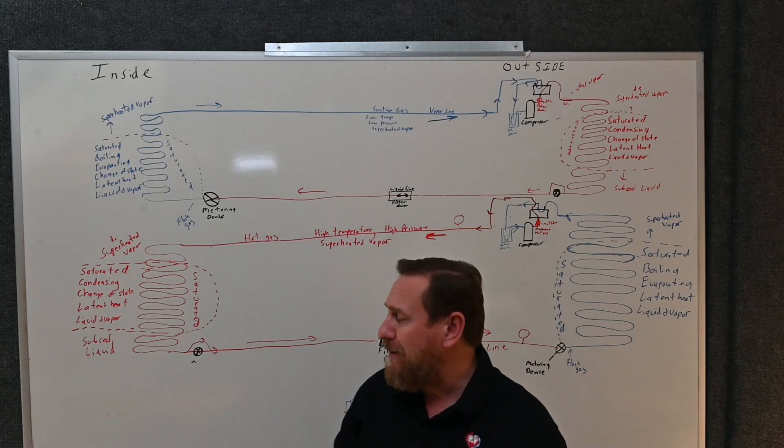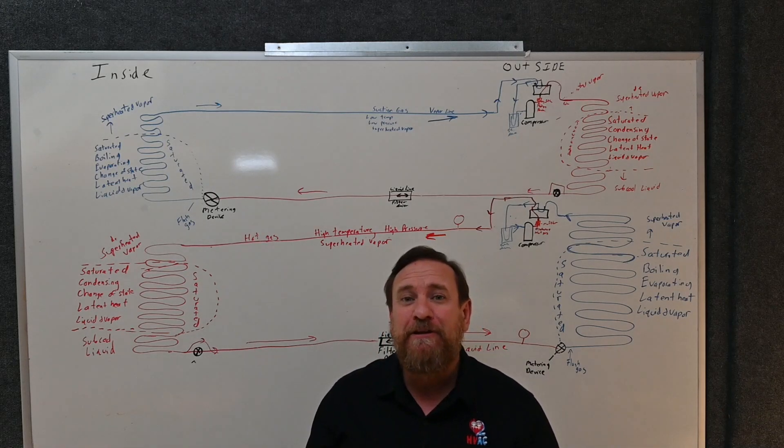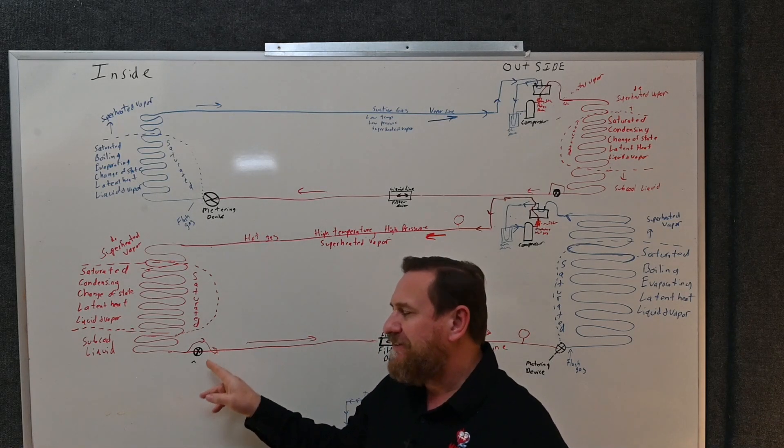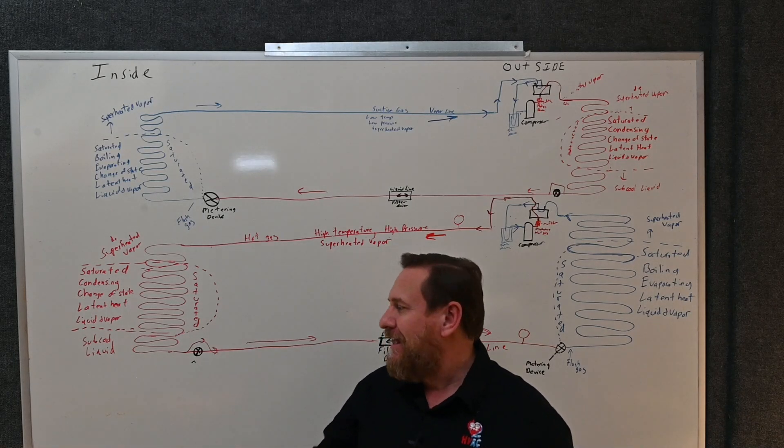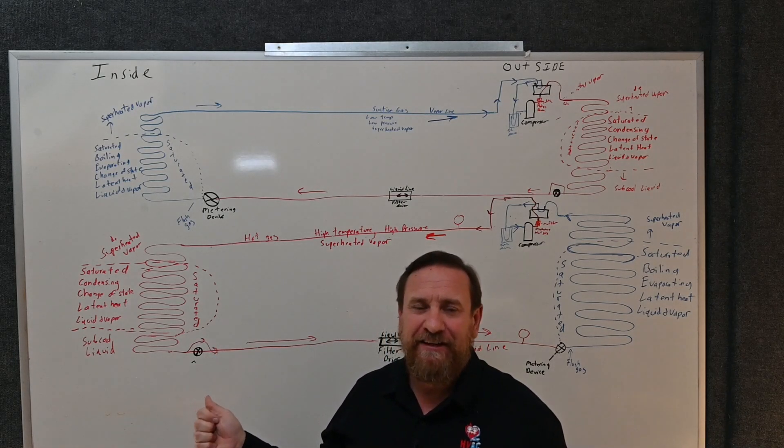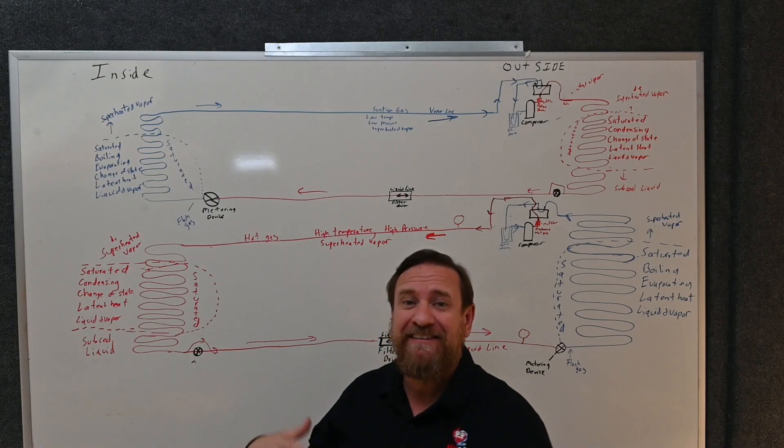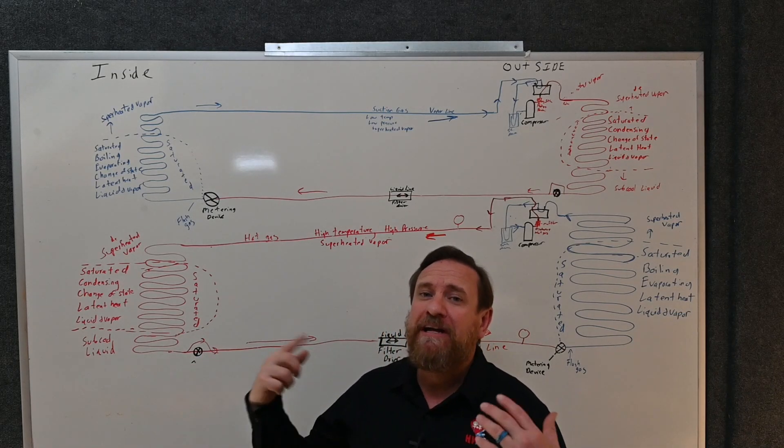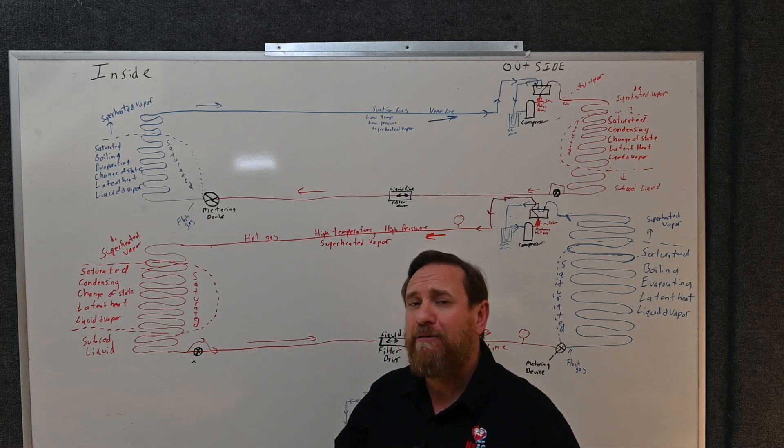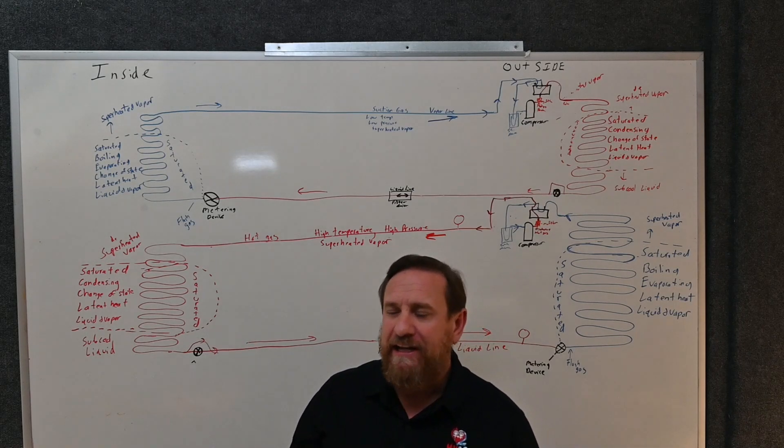I want to note that a lot of people blame that TXV first, but notice in this scenario it wasn't that the TXV failed. It was contamination in that system that clogged up those moving parts in the TXV, so it wasn't its fault. The fact that the system was dirty and contaminated. So we want to keep that in mind. If we have that issue, we want to make sure we clean up that system so we don't have that same problem on the new metering device we're putting in there.